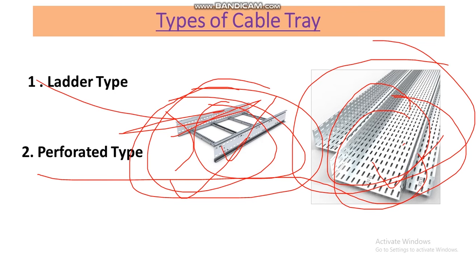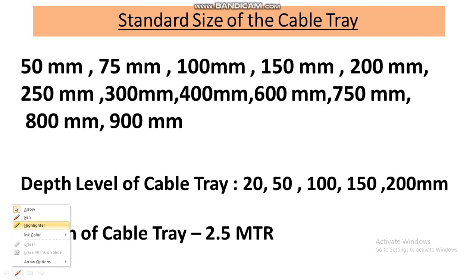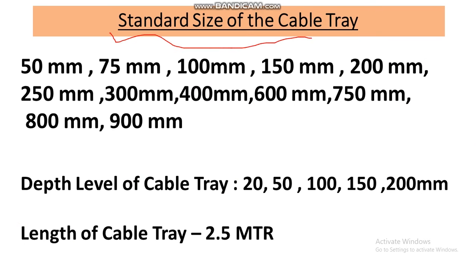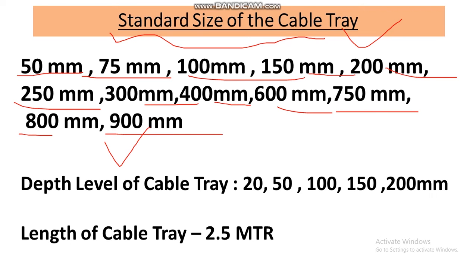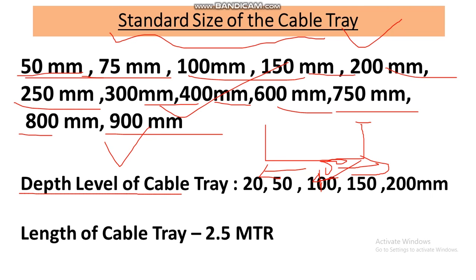Now let's look at cable tray sizes. The standard sizes available in the market for width are: 50mm, 75mm, 100mm, 150mm, 200mm, 250mm, 300mm, 400mm, 600mm, 800mm, and 900mm. The depth sizes available are: 20mm, 50mm, 100mm, 150mm, and 200mm. The standard length of a cable tray is 2.5 meters.